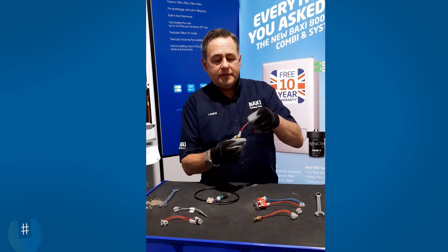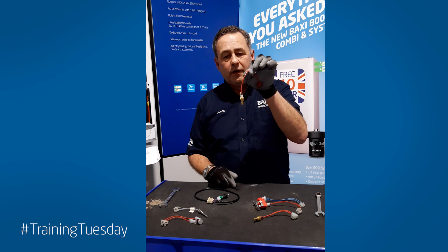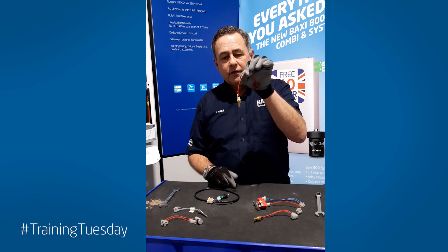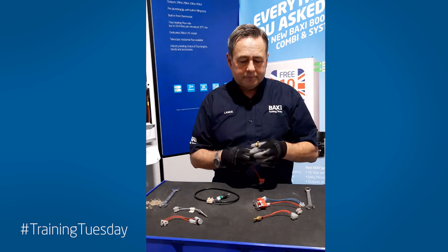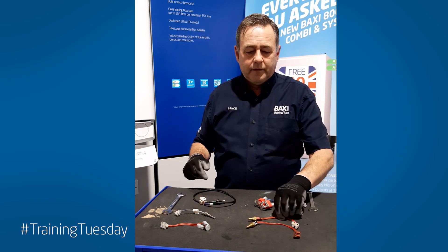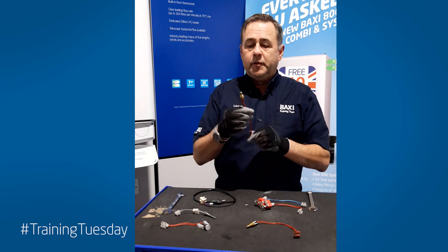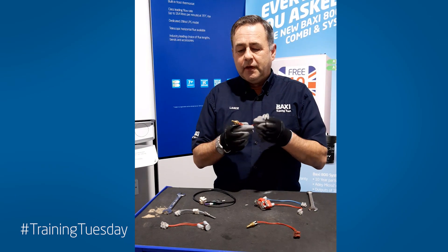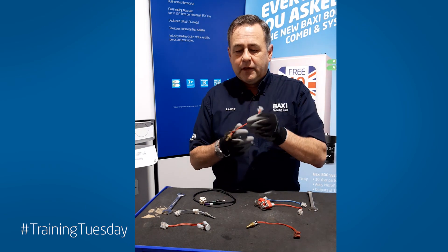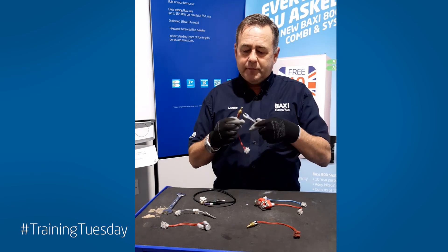This one is out of the older 105 or Potterton Performer combination boilers. Two of them, one for hot water, one for central heating, 13 mil spanner to remove them. This one is the later version out of the Duo-tec, the Platinums, the Potterton Promax combination boilers and the Main Eco Elite for hot water. Used for hot water and heating, 13 mil spanner.